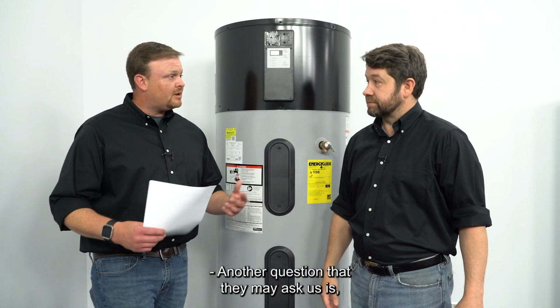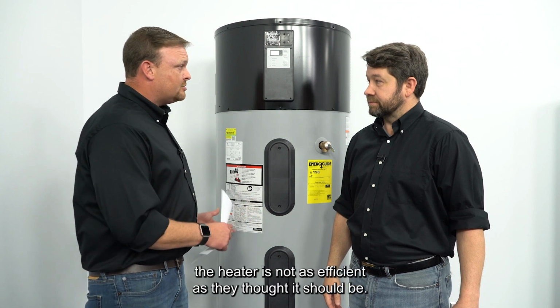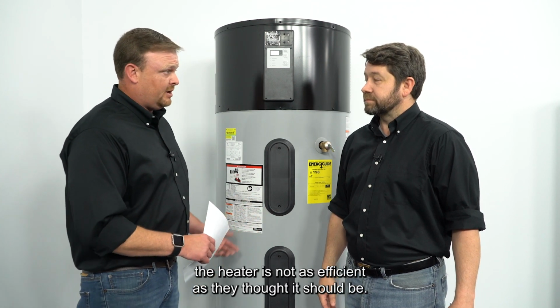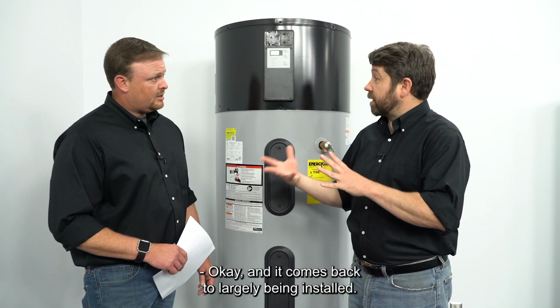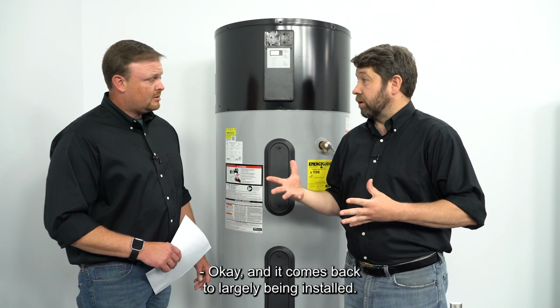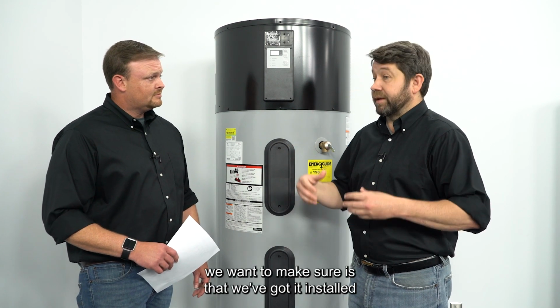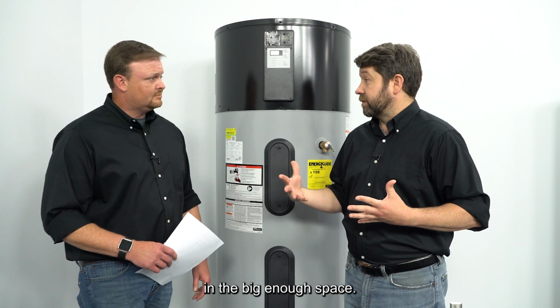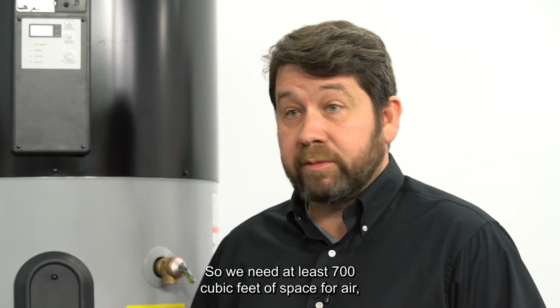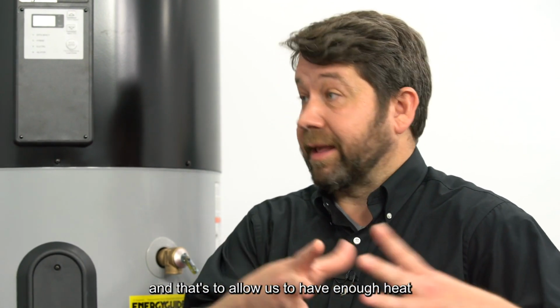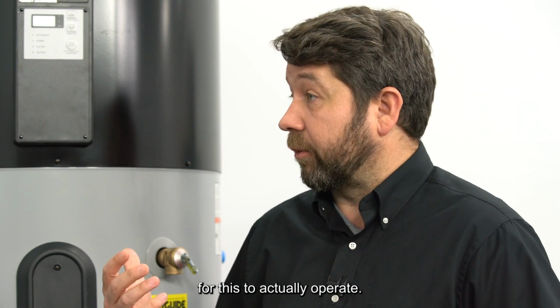Another question that they may ask us is, the heater's not as efficient as they thought it should be. And that comes back to largely being installed. Right. So the first thing we want to make sure is that we've got it installed in a big enough space. So we need at least 700 cubic feet of space for air, and that's to allow us to have enough heat for this to actually operate.